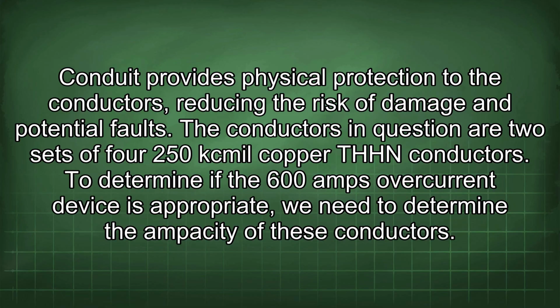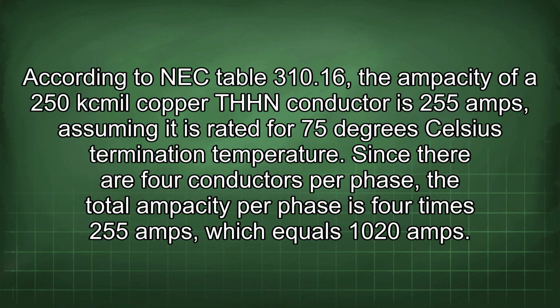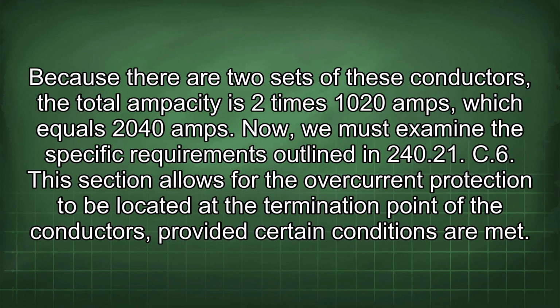The conductors in question are two sets of four 250 kcmil copper THHN conductors. To determine if the 600 amp overcurrent device is appropriate, we need to determine the ampacity of these conductors. According to NEC Table 310.16, the ampacity of a 250 kcmil copper THHN conductor is 255 amps, assuming it is rated for 75 degrees Celsius termination temperature. Since there are 4 conductors per phase, the total ampacity per phase is 4 times 255 amps, which equals 1020 amps. Because there are 2 sets of these conductors, the total ampacity is 2 times 1020 amps, which equals 2040 amps.